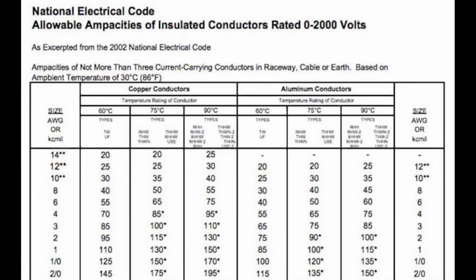This is probably the most important part of this entire video. It's the National Electric Code allowable ampacities of insulated conductors rated from 0 to 2000 volts. This is from the 2002 version of the National Electric Code, but it has not changed. It is still the same in 2022. If we start from the top, we will see that it tells you what material the wire is made out of. It gives you a choice of copper or aluminum conductors. And below that, we've got a row of temperatures. Those temperatures tell you where it is still within the range of the wire to handle the current.